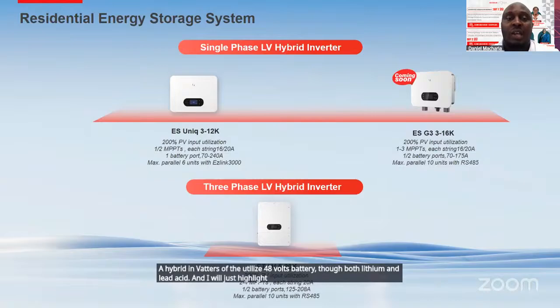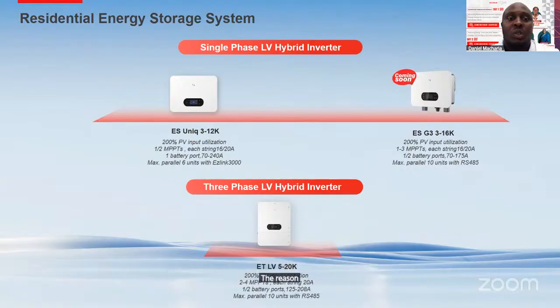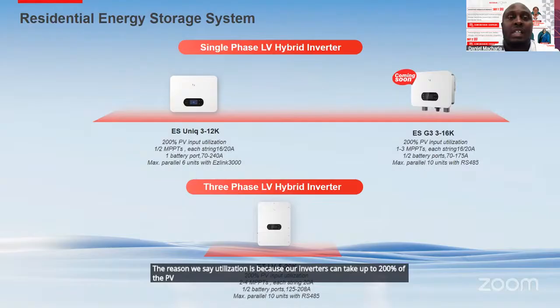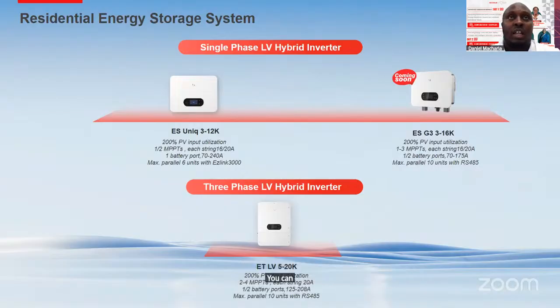Key features of our hybrid inverters, starting with PV utilization. We say utilization because our inverters can take up to 200% of PV, depending on the capacity of the inverter. So if you have a 12 kilowatt inverter, you can install 24 kilowatt peak capacity of panels and be able to utilize all of it.